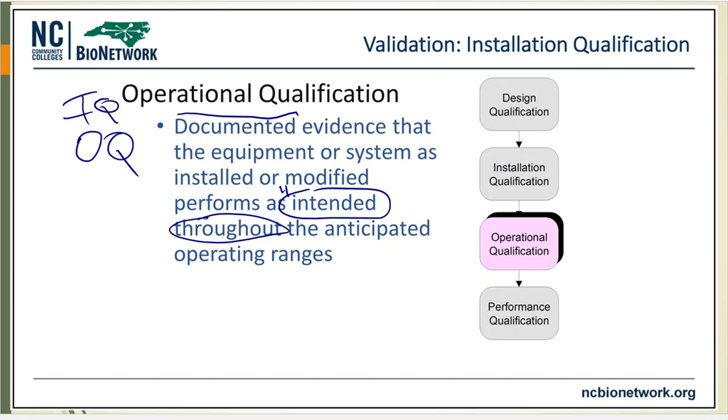All right, well, I'm going to get a report from that, and that report is the operational qualification. This is what I wanted. This is the specific things that we're doing with it, and this is what I'm after. So please prove to me that it can do those things, because you told me it could when you sold it to me. So this is the operational qualification that's happening here.